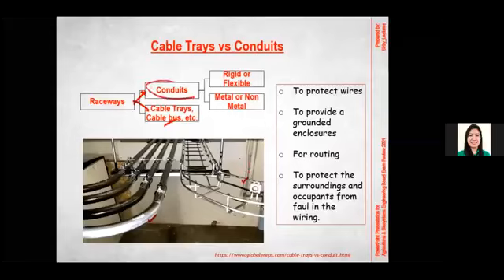But we'll only focus on conduits. Conduits are a type of raceway, and their function is protection - they protect wires from external damage. One function is that if there's a fault in the wiring, it can provide protection for the occupants. If the problem is inside, the occupants or building would be safe, and if the problem is outside or external to the wiring, it can give protection to the wirings. It also provides grounded enclosures and is used for routing.